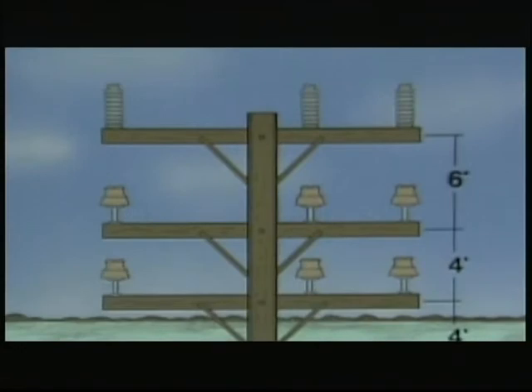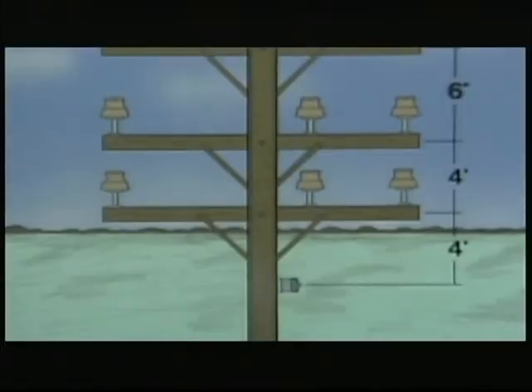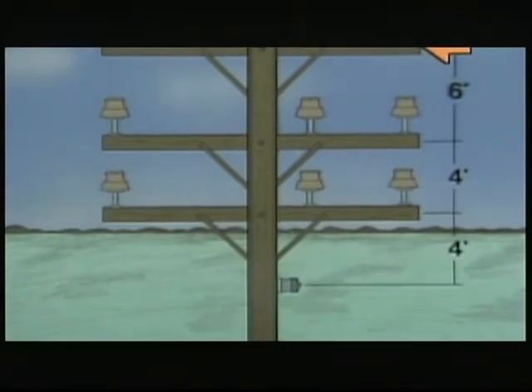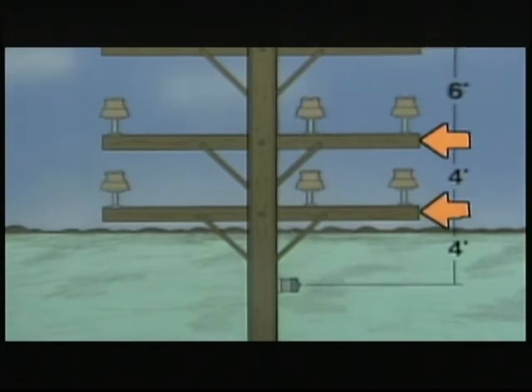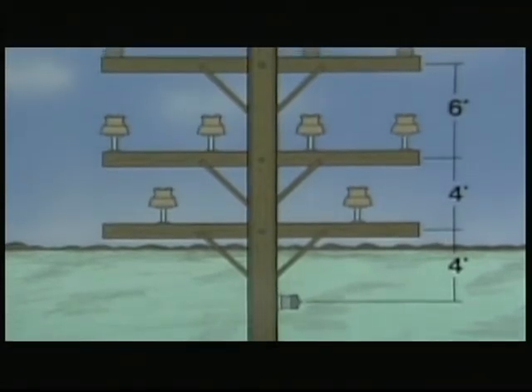Many poles carry more complex circuit arrangements. Using a simplified illustration, on this pole the sub-transmission circuit is here and one primary circuit is here. A good way to distinguish between circuits of different voltage levels is to check the spacing between them. In this system, sub-transmissions are six feet from the primaries, the primaries are four feet apart, and the bottom primary is four feet from the neutral.